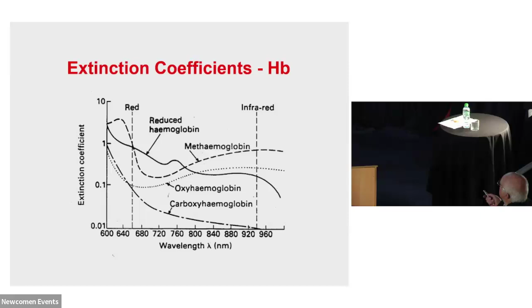The next most dangerous one, and the most important one, is abnormal hemoglobins. Now, we've pointed out the red and the infrared of the normal oxyhemoglobin and hemoglobin without enough oxygen. It's the ratio between those two. Unfortunately, carbon monoxide really screws the whole system up. So does methemoglobin, which is quite rare, but carboxyhemoglobin is fairly common.